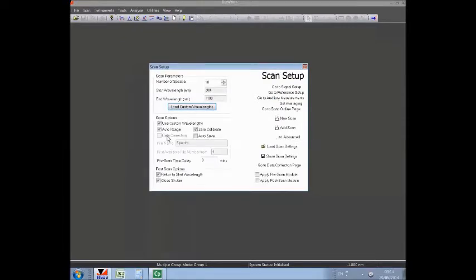We should go into advanced and ensure that data correction is not selected for this measurement, which is a system calibration. We should check, however, that auto range and zero calibrate are always selected. We need not touch those. In terms of number of spectra, I would typically select 10. The reason being that we need to allow for a lamp warm-up time, which we may say is 5 to 10 minutes.